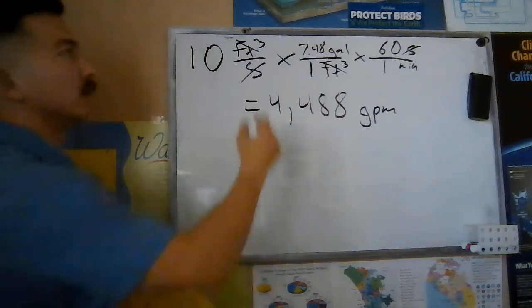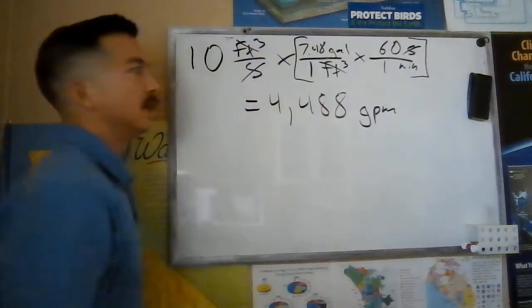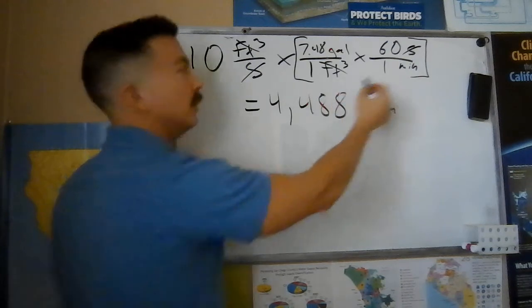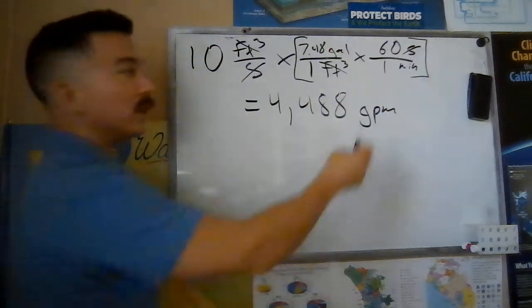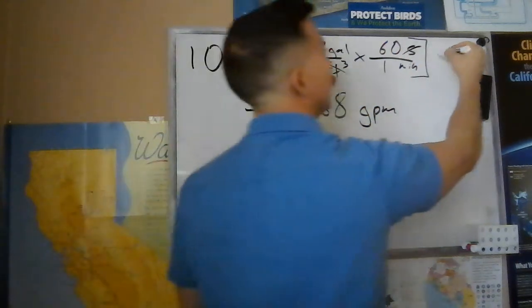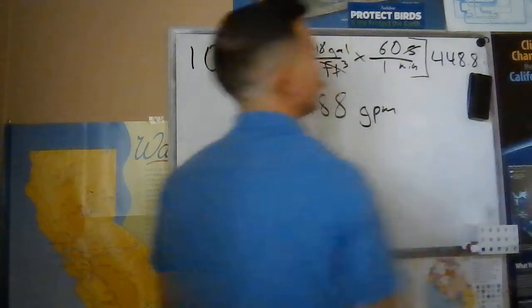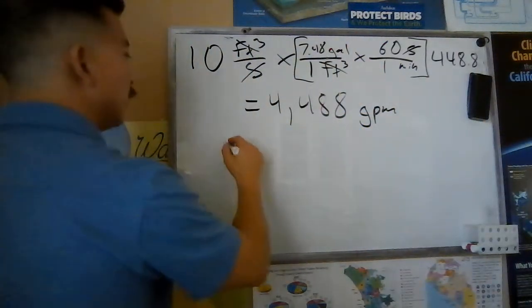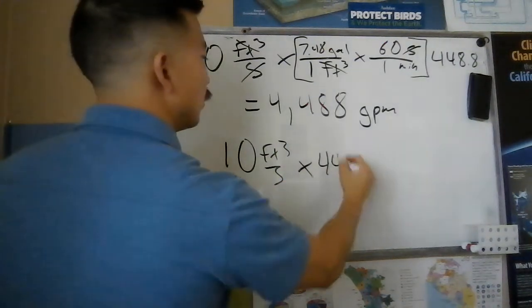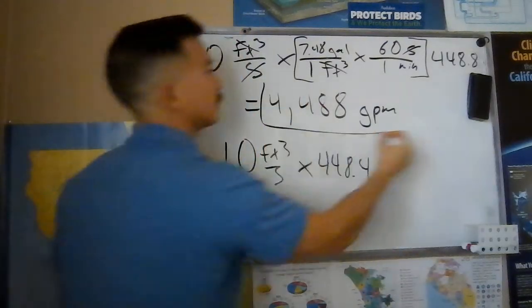Now I want to point out the shortcut here in that this part of the conversion factor here is always going to be the same. We're always going to use 7.48 gallons per cubic foot, 60 seconds per minute. So when we come in here and multiply 7.48 times 60, just the brackets here, we're going to get 448.8. So that is a shortcut you can use. So for this problem, we could just do 10 cubic feet per second times 448.8. And that's going to get us to our same answer here.